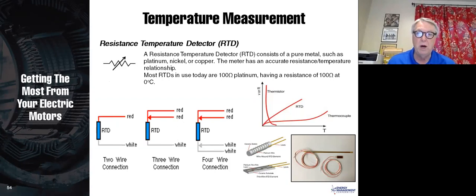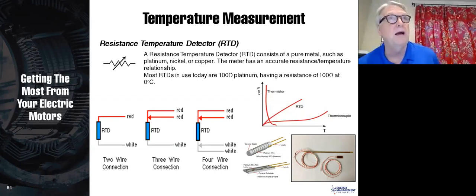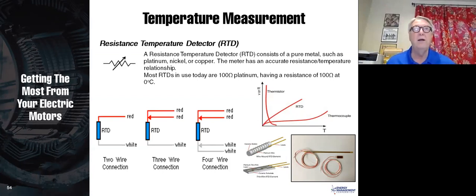So what you have here with 3 wires is you have 2 reds and 1 white. When you measure the temperature, you put current through here, or you have a voltage across here actually, and then you measure the current, and that tells you the resistance. But you put in another wire and it tells you the voltage right here at the RTD. And since there's no current in this wire, by looking at the difference between this wire and this one, you can tell what the voltage drop was across the wire. And then you can subtract that voltage drop in the temperature detector, and basically you're measuring the RTD and the wire, but then you're backing out the resistance of the wire. They're assuming that the resistance of the white will be the same. So you basically take the voltage drop here on red and you double that, because you're also accounting for the white.